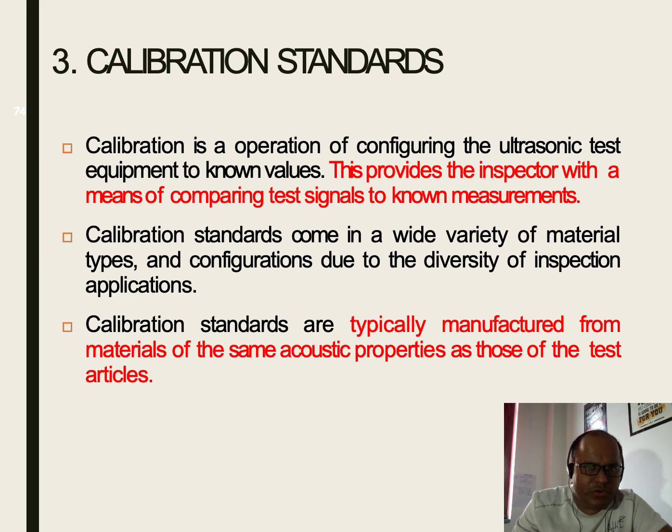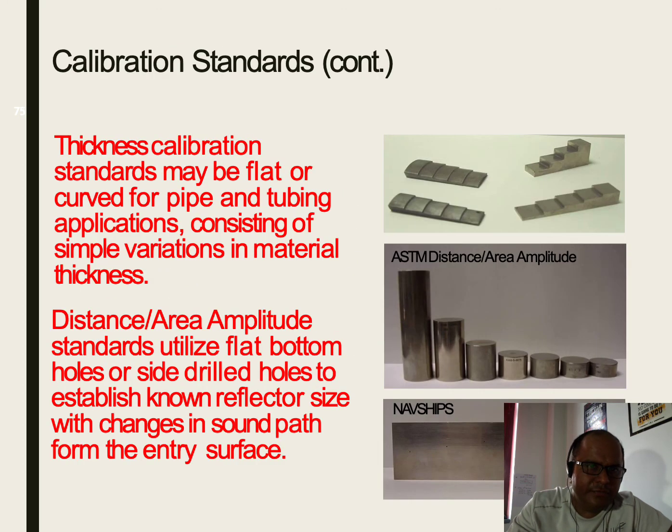Calibration is the operation of configuring the ultrasonic test equipment to known values. This provides the inspector with a means of comparing test signals to a known measurement. Calibration standards come in a wide variety of material types and configurations due to the diversity of inspection applications. Calibration standards are typically manufactured from material of the same acoustic properties as those of the test articles.